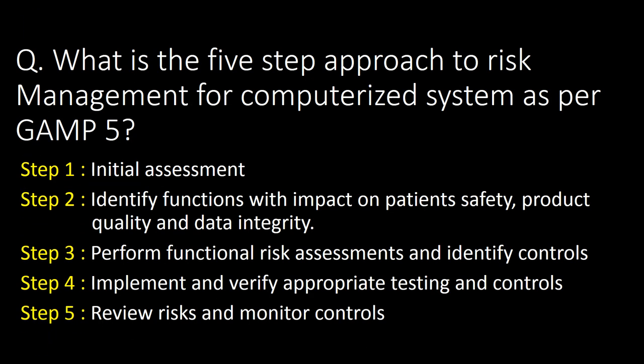What is the five-step approach to risk management for computerized systems as per GAMP-5? Step 1 is initial assessment. Step 2 is to identify functions with impact on patient safety, product quality, and data integrity. Step 3 is to perform functional risk assessment and identify controls. Step 4 is to implement and verify appropriate testing and controls. Step 5 is to review risk and monitor controls.